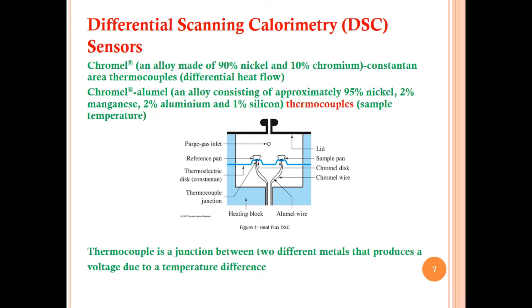The sensors in the DSC instrument include chromel, an alloy made of 90% nickel and 10% chromium, and constantan — these are area thermocouples measuring differential heat flow, which is the difference in heat between the sample and reference. Chromel-alumel is an alloy of approximately 95% nickel, 2% manganese, 2% aluminum, and 1% silicon, and is also a thermocouple that measures sample temperature.